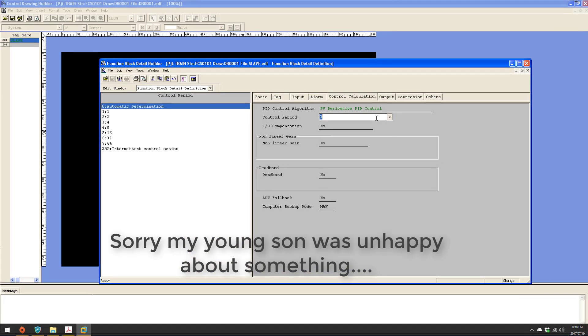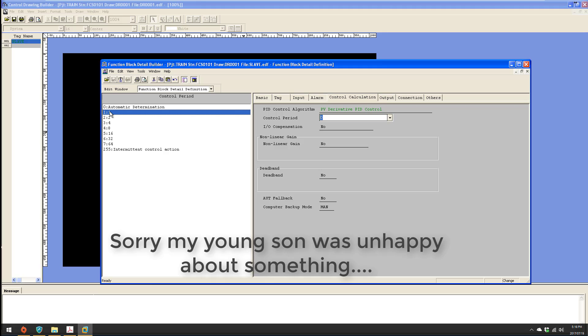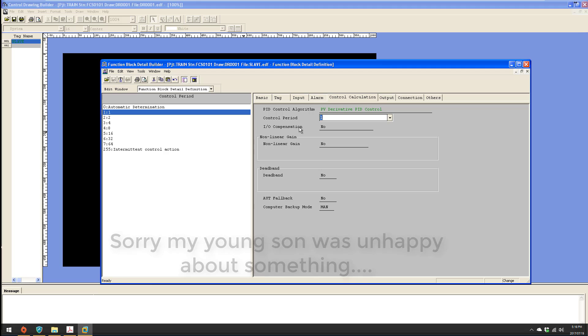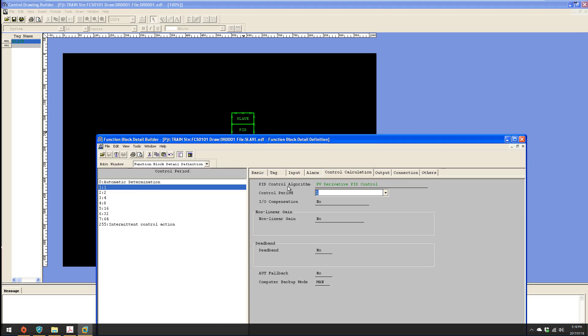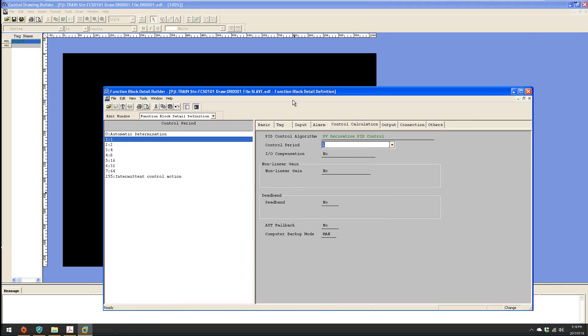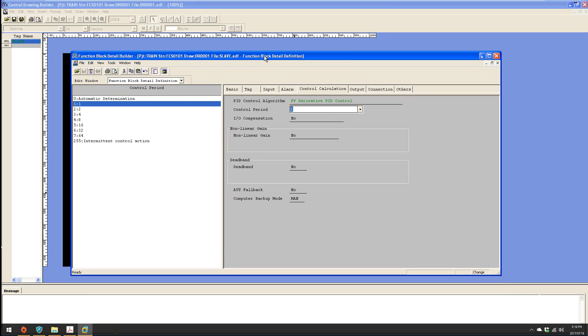What we normally do is, if it's a key loop that needs a high scan rate, you uncheck automatic determination and set it to one. That guarantees it's going to scan every scan period for that block. Those are two very key hidden pieces of information on the Yokogawa that very few people really know, and I want to make sure you use them correctly.